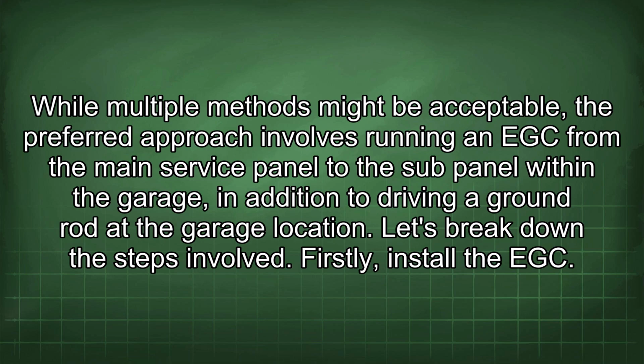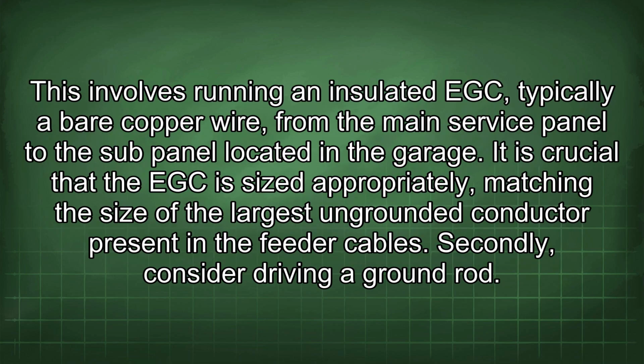Let's break down the steps involved. Firstly, install the EGC. This involves running an insulated EGC, typically a bare copper wire, from the main service panel to the sub-panel located in the garage. It is crucial that the EGC is sized appropriately, matching the size of the largest ungrounded conductor present in the feeder cables. Secondly, consider driving a ground rod.